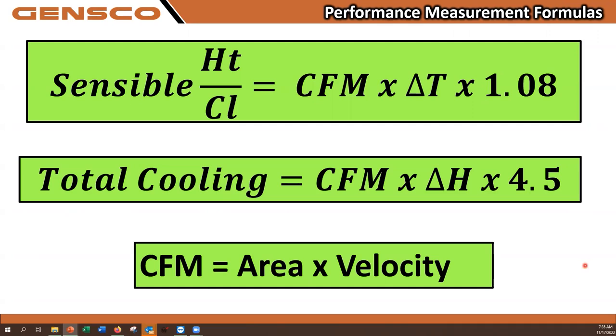If you are trying to do a cooling check and you don't have a psychrometer, you can use a thermometer to do the sensible cooling. It's just the temp split times the CFM times 1.08, and add 25% to it. You'll be in the ballpark. It won't be 100% accurate, but you'll be close, because again, most units do about 25% latent cooling. But this could save you from spending a couple hours in the rain or the snow, driving wind, pulling charge to find out you're 2 ounces low, not 2 pounds. So I'm not concerned about 2 ounces. And if it doesn't do the BTUs that it should have been doing, it's time to pull the charge.